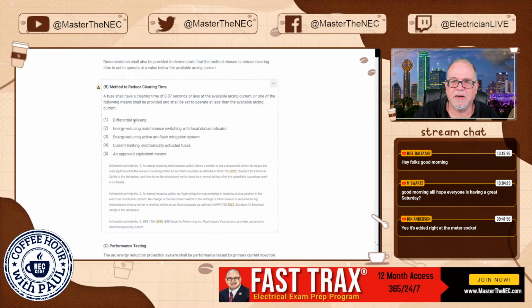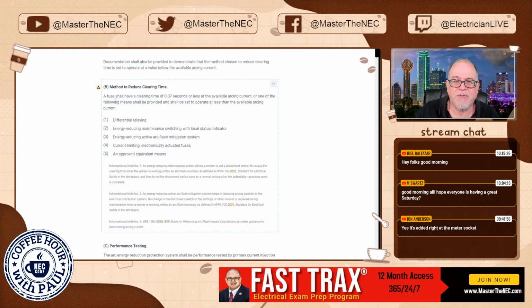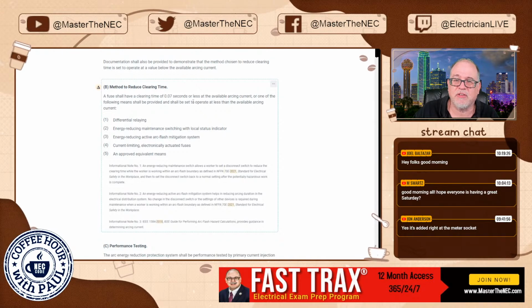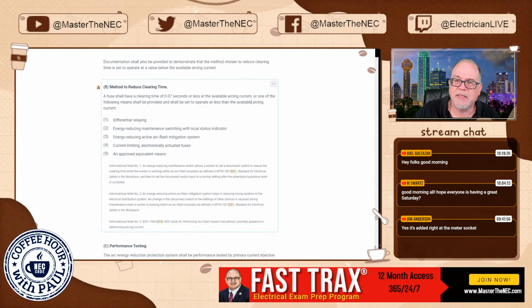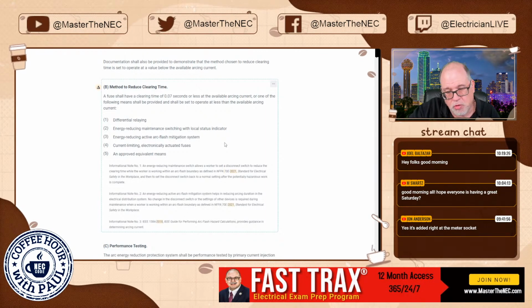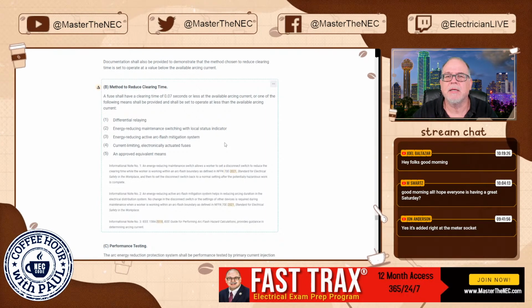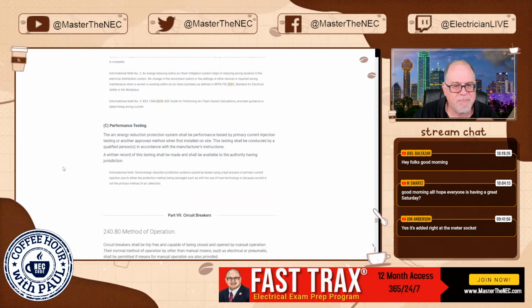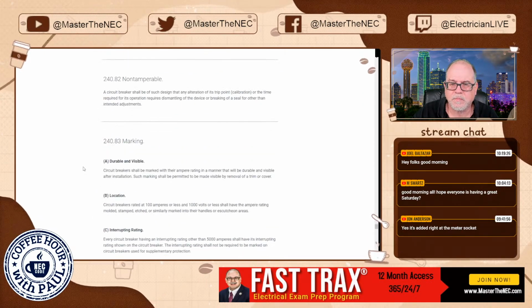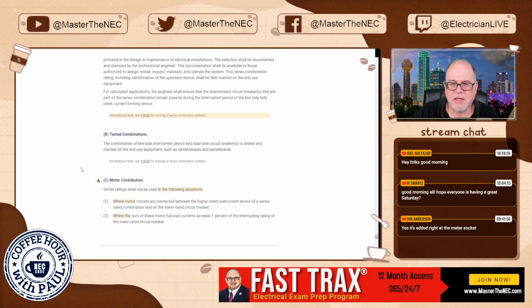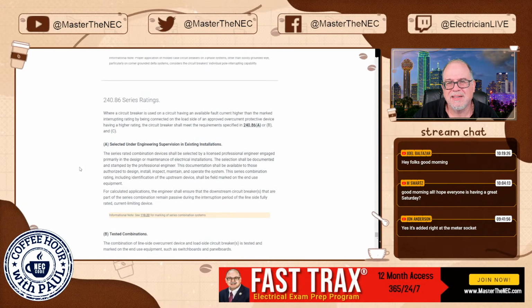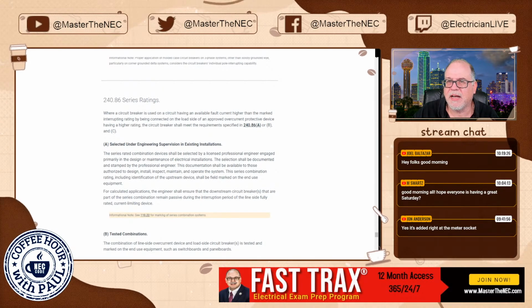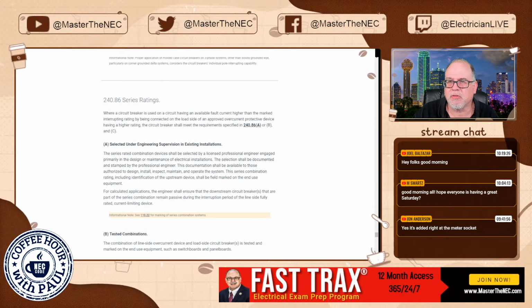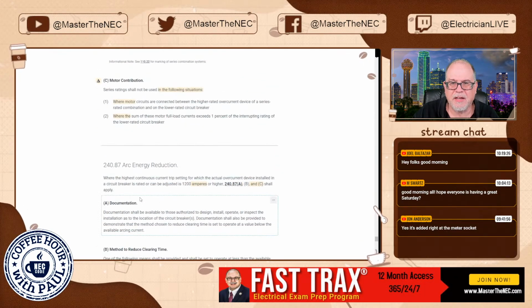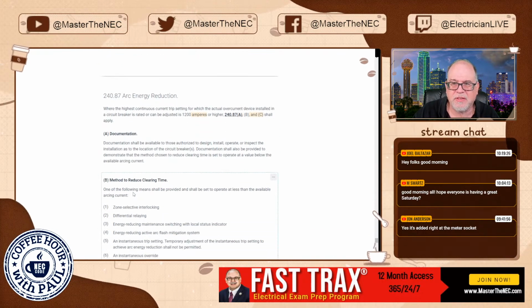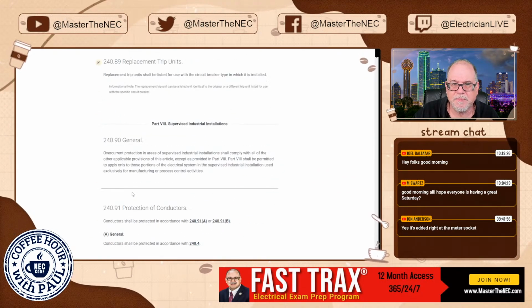Here, methods to reduce the clearing time. Okay, a fuse shall have a clearing time of 0.07 seconds or less at an available arcing current. Work with your manufacturer, look at fuse curves and plot it out. All right, but you have these options. So again, pretty much the same as it was before. Let's see here. Let me see if I've got any more on my mind that I want to make sure I'm covering. No, that's not significant enough. These are just verbiage changes. That's pretty much what we had before.